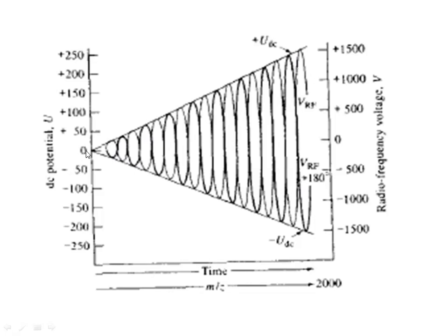The values we have gradually increased. We have increased the value for AC as well as DC voltage. Ultimately, the ratio is kept close to 6. So by changing the amplitude of AC and DC potentials, we can bring different m/z values to focus, and then they can be measured.